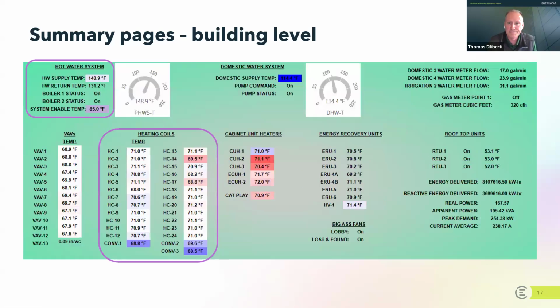Let me take you to the next one. A couple of things I wanted to talk about here. I mentioned in the previous slide the hot water supply temperature and hot water return temperature. This represents a system that's actually heating, right? The supply temperature going out is 149, and it's coming back at 131. It means that there is heat being lost in the system.